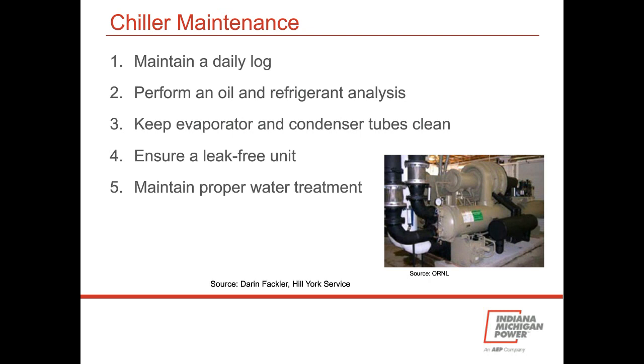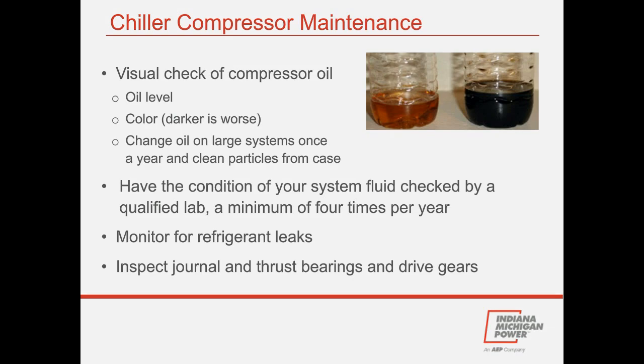And you can see kind of a difference here in the 2 bottles, the compressor oil on the left versus the right. Darker is more contaminated oil, older oil, and you want to change that at least once a year, and send fluids, oil and refrigerant, to be checked by a qualified lab on a regular basis. Obviously, you want to look for leaks. A lot of spinning components here, so journal, thrust bearings, drive gears are important things to check out as well.